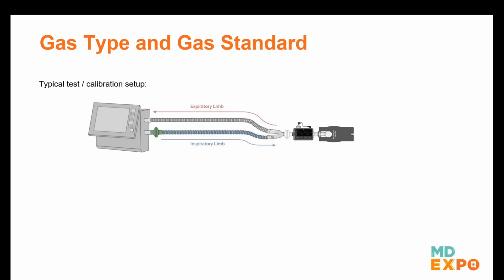Okay, well, how does that affect us? When we test a ventilator, what do you use to test it with? Is there a humidifier in line? Are you humidifying the gas? Or are you just simply connecting your ventilator to your analyzer, right? So here, again, if our ventilator is displaying BTPS, let's say we've typed in 560 as a setting, and the ventilator's spirometry is telling us, yep, you're giving 560 out. Well, in reality, when it gets to our analyzer, it's not really 560, right? It's going to be about 500.